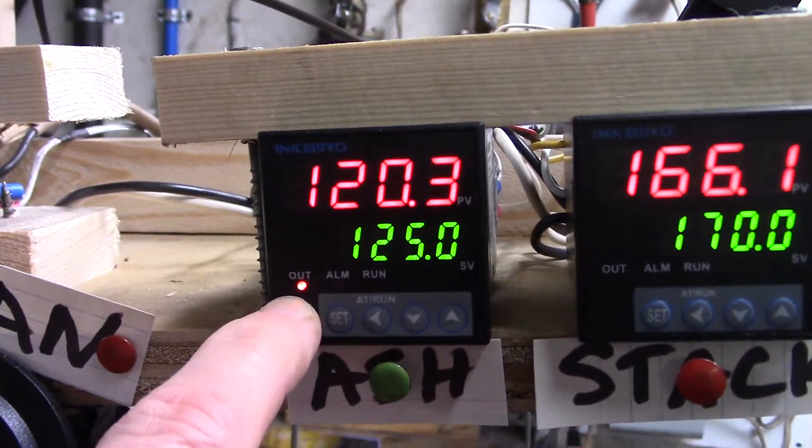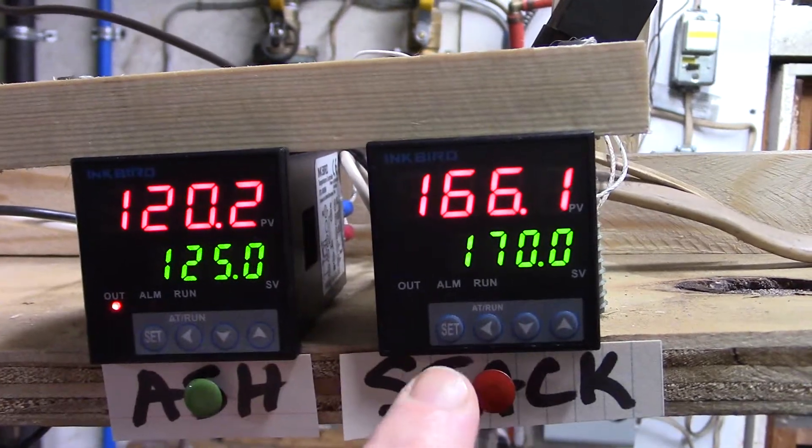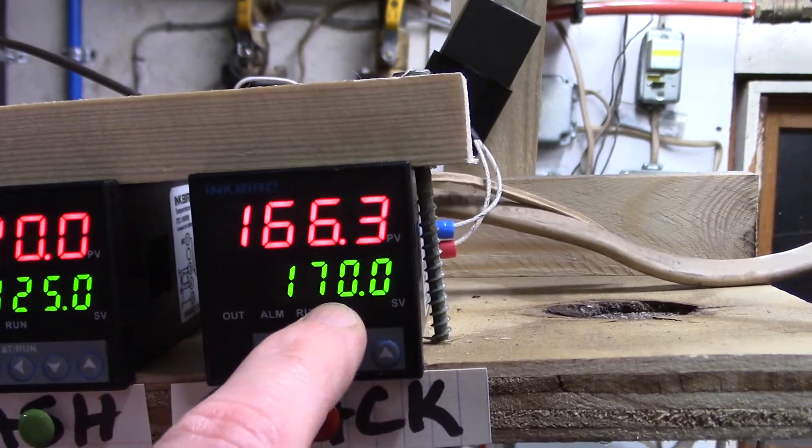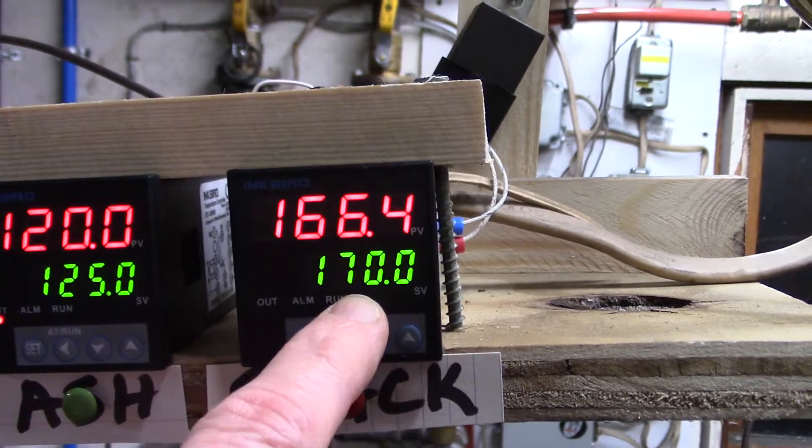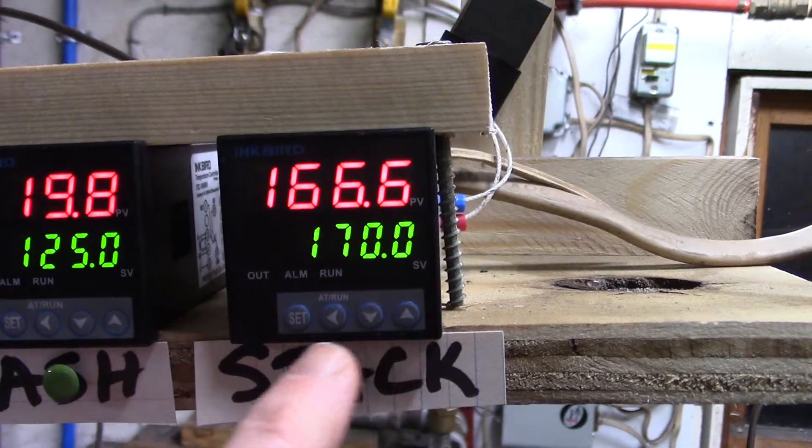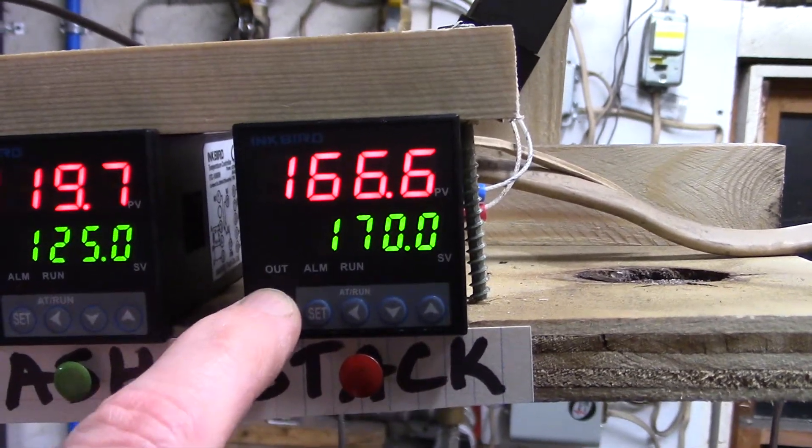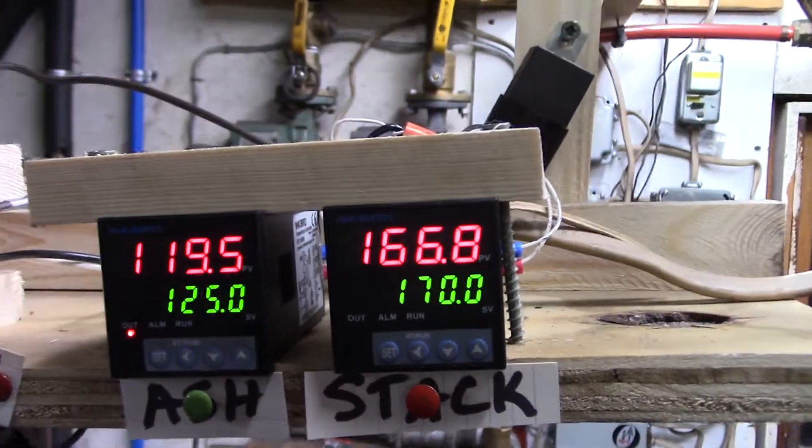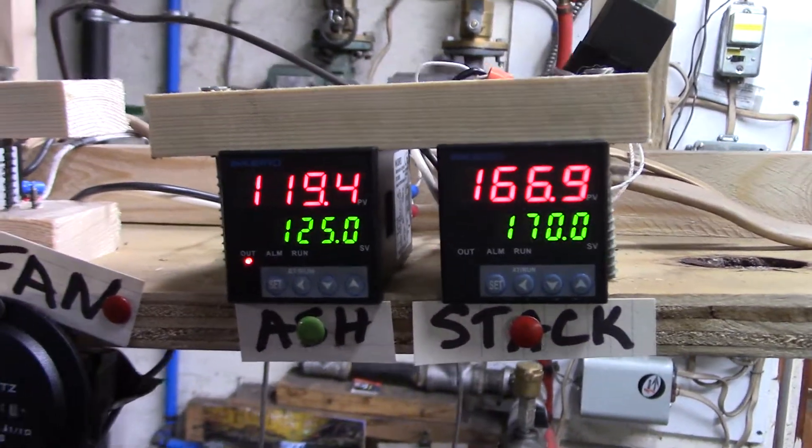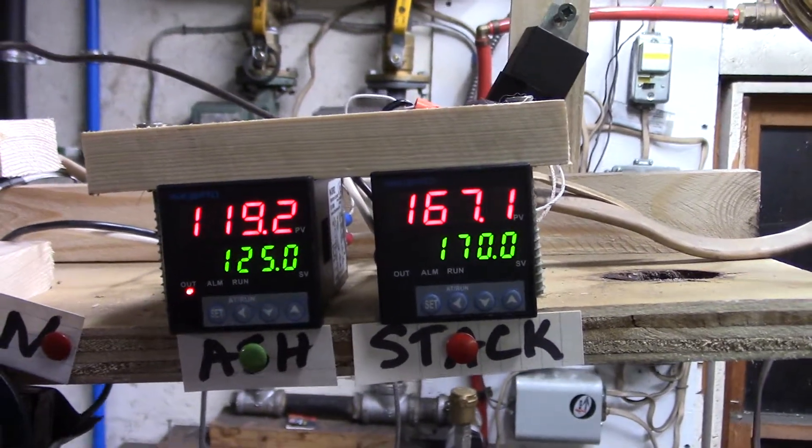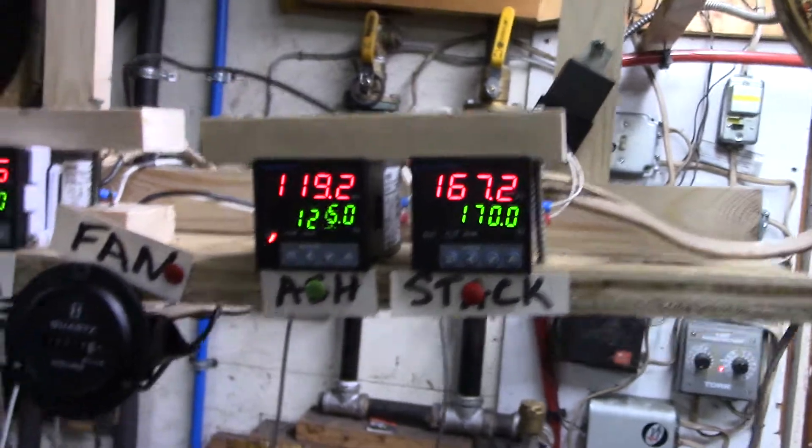The ash temperature is below the 125 degree set point so this relay is activated. These two relays are in series. The stack temperature has not reached the 170 degrees set point yet but it will in a few seconds, and once it does this little red light will come on, the relay will activate, and then the auger will start turning and the solenoid will activate.